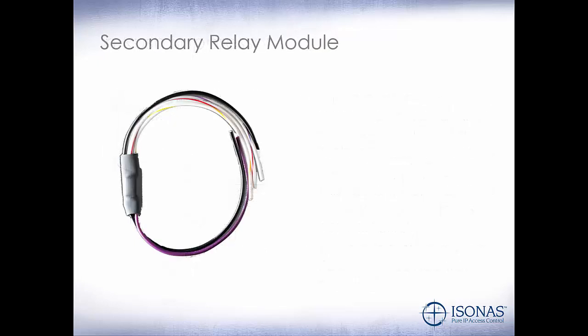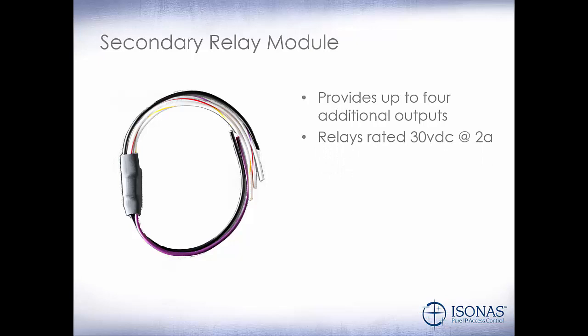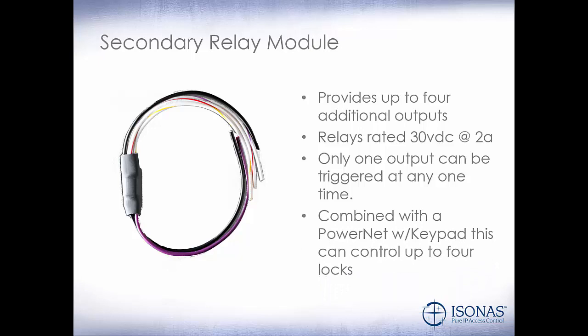How do we use the TTL outputs on our PowerNet reader? We use the secondary relay module. It provides up to 4 additional outputs. The relays are rated at 30 volts DC at 2 amps. However, only one output can be triggered at any one time. So if you want to use both TTL outputs on your PowerNet reader and they may be both activated at the same time, you'll want to use two secondary relay modules — one for each TTL output. Combined with a PowerNet with keypad, this can control up to 4 locks for data centers and medical cabinets, where only one lock will be opened at any one time.